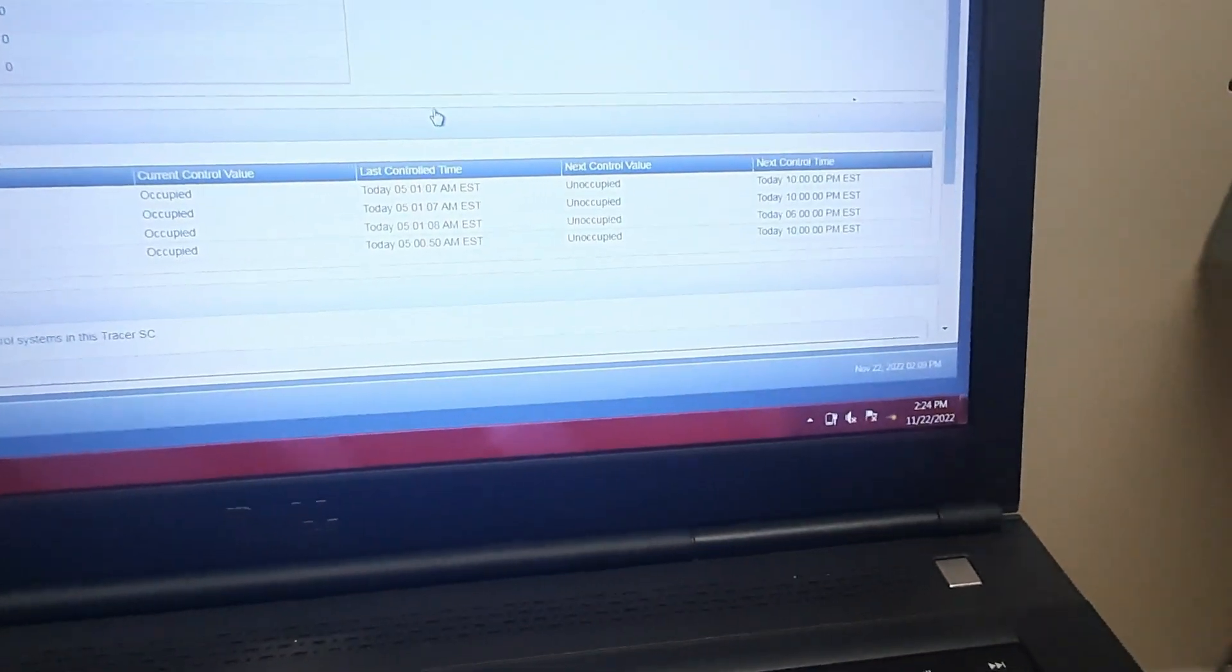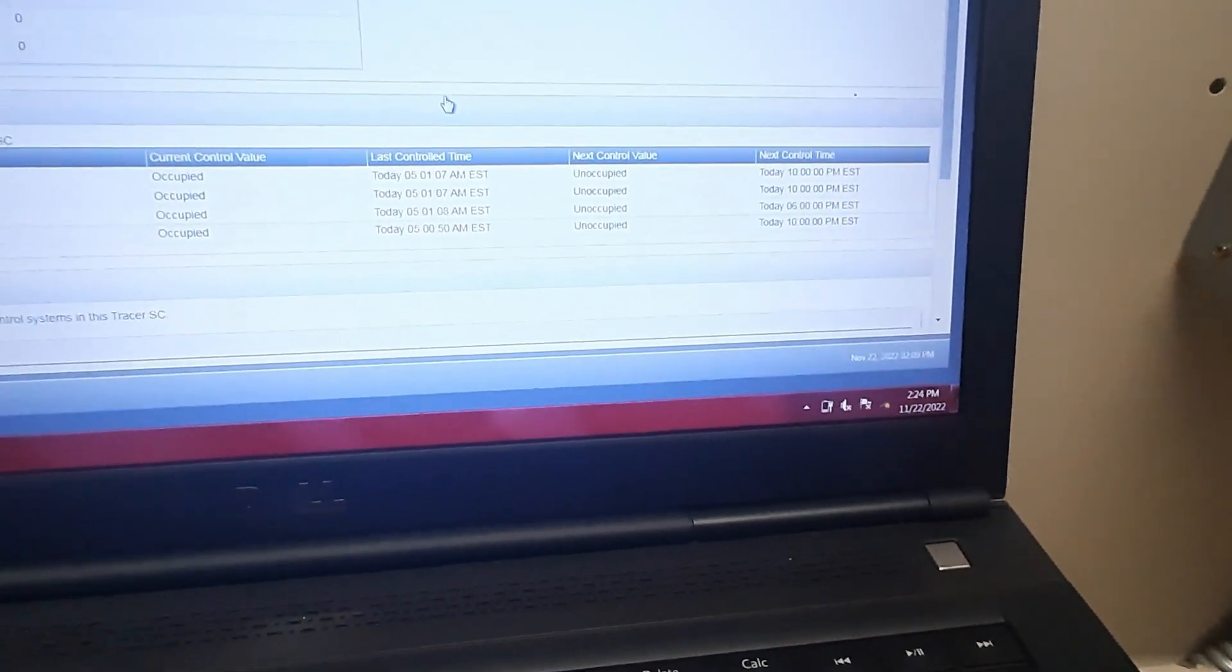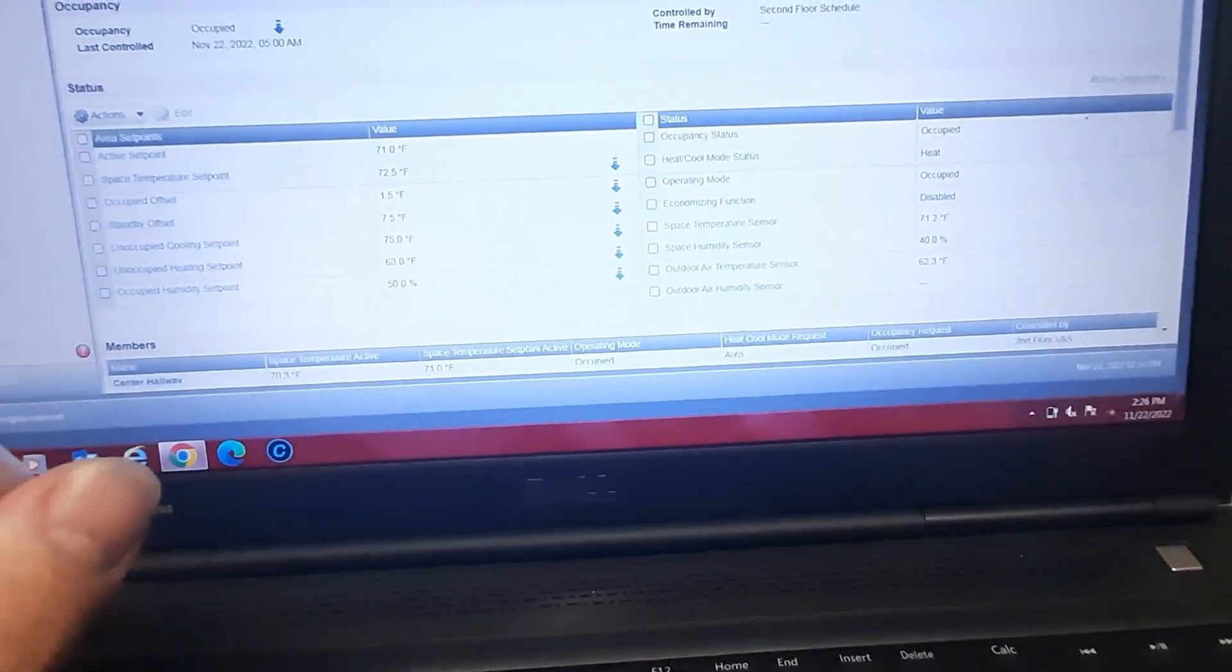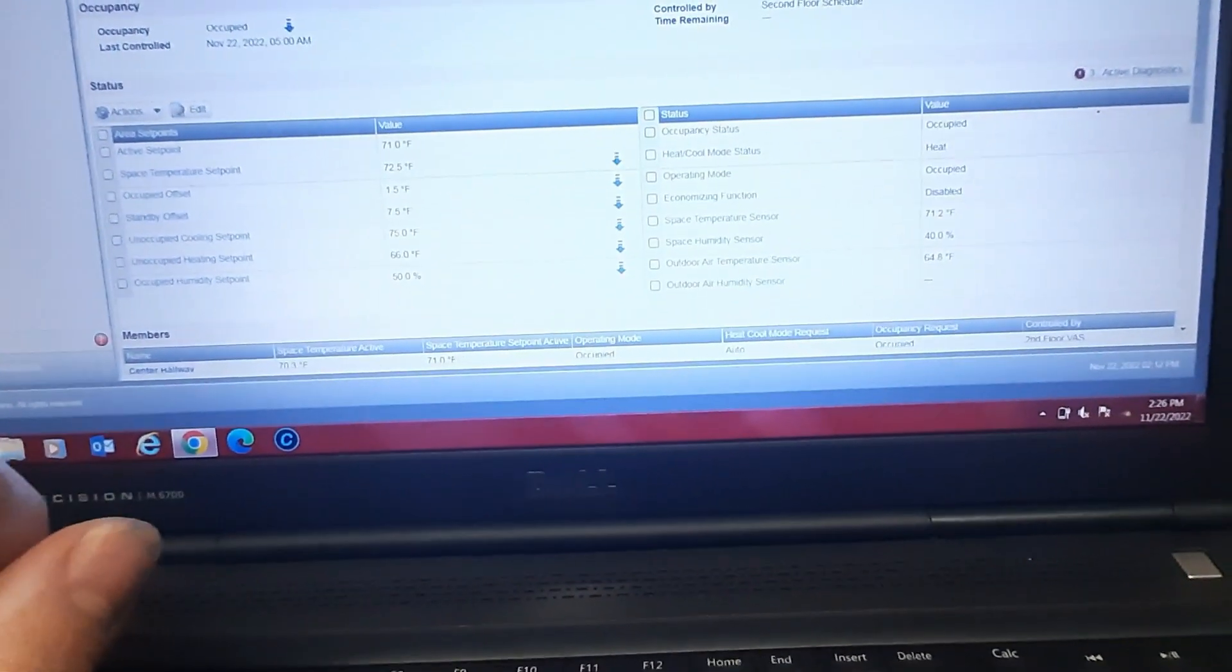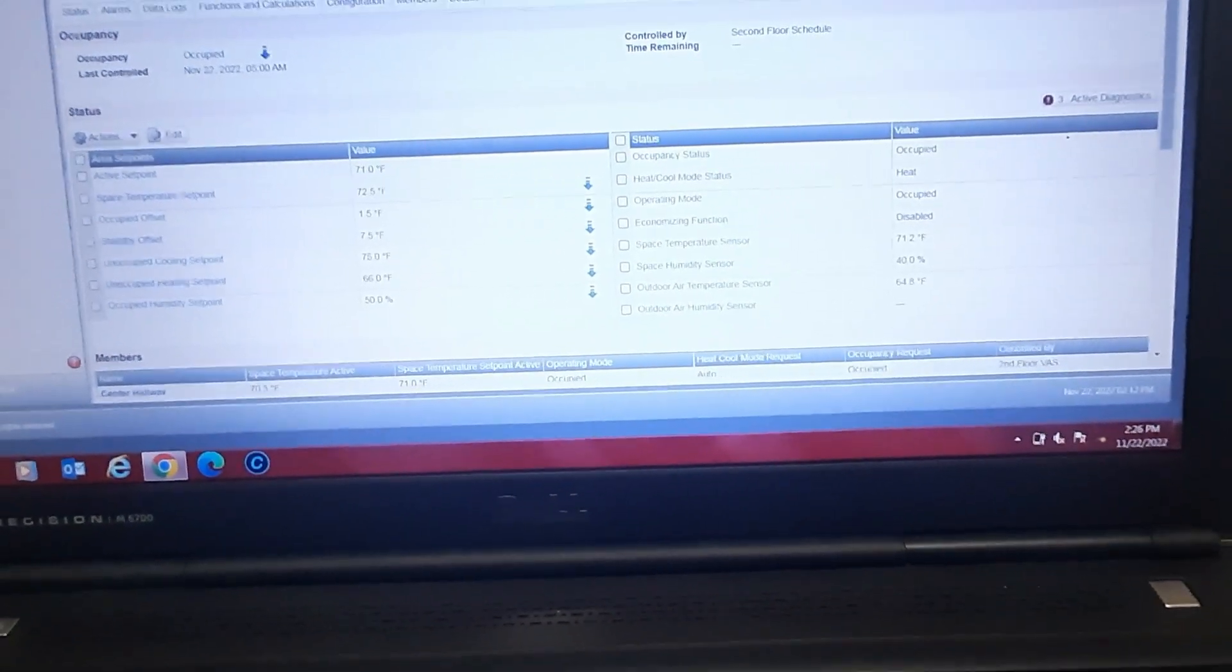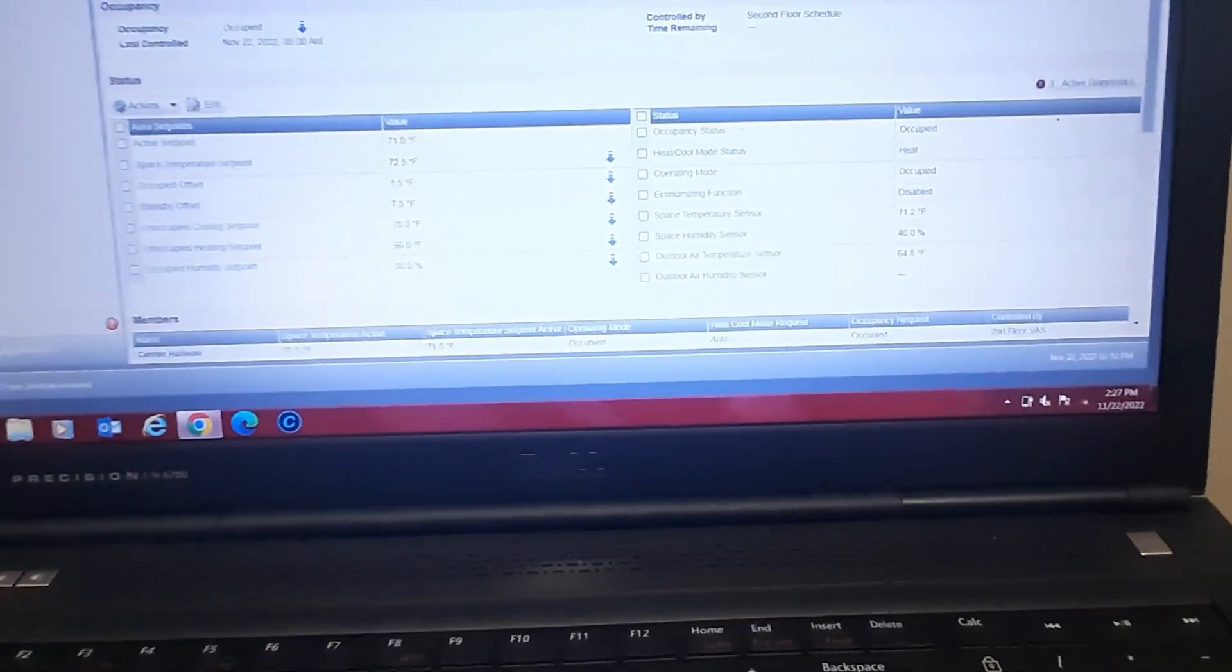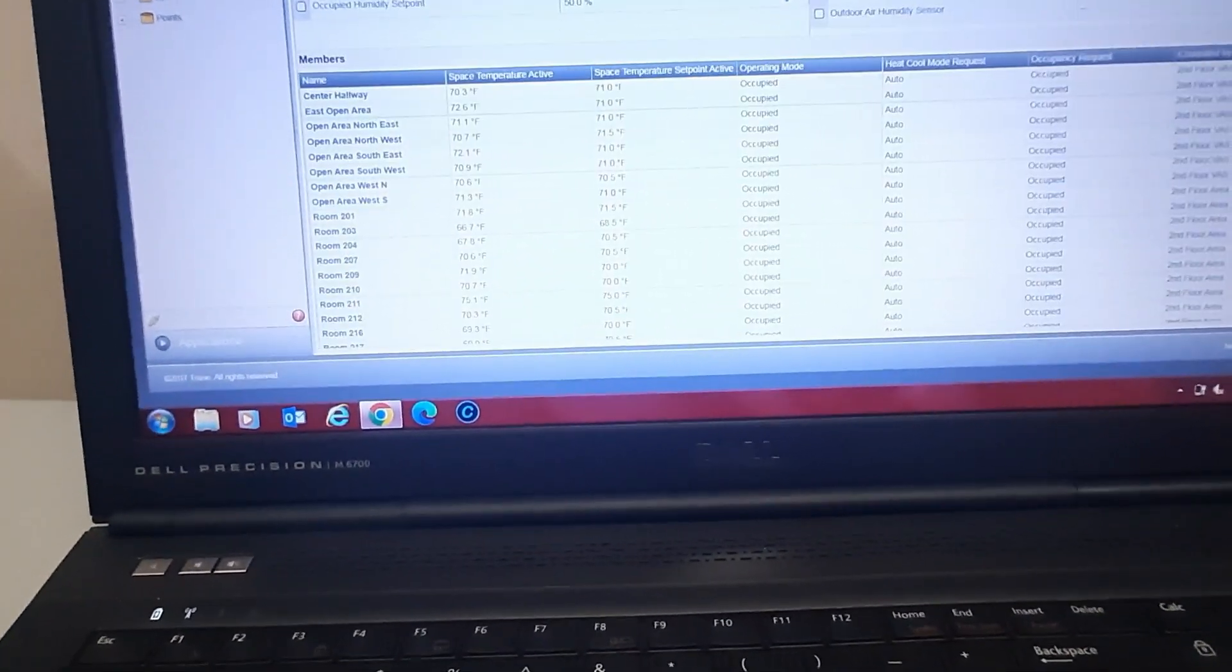So we're gonna scroll through and find the right space first and then we'll find our VAV boxes that are in question. I'm in areas now, this is my second floor area. I changed the unoccupied heating set point, was 63, went up to 66. Everything else looks fairly normal. Space temperature sensor's 71. The outdoor temperature's off, it says 65 almost. It's probably in the sun would be my guess. It's probably 45, 50 outside. We've been having cool mornings and warmer afternoons.